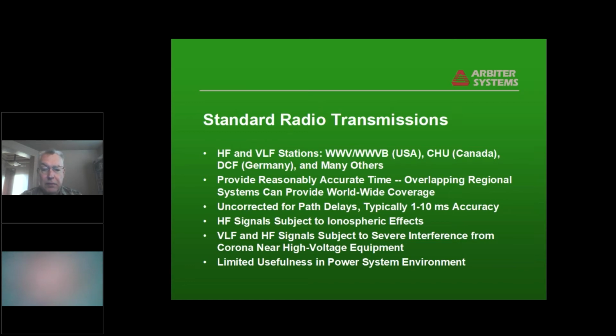Whereas WWVB and DCF, for instance, operate in the low frequency band that has the potential of providing around a millisecond accuracy, which is good enough for some applications. But one of the big problems with these signals, as I mentioned, is that the high frequency signals are subject to serious ionospheric variations. But the VLF signals, like the WWVB and DCF, are also subject to interference from corona near high voltage equipment. That limits the usefulness that the system has for power applications.